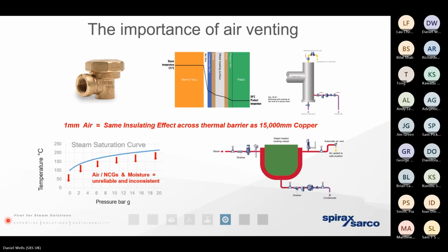And the other problem with having too much air in a steam system is, well, it's like failing to bleed your radiators at home. That air is a massive, massive barrier to heat exchange. It's going to cause the process time to slow down, and therefore the heat exchanger is going to call for more and more steam. The boiler's got to work harder, and the cost of steam, the cost of gas, and those carbon emissions are all going to increase.